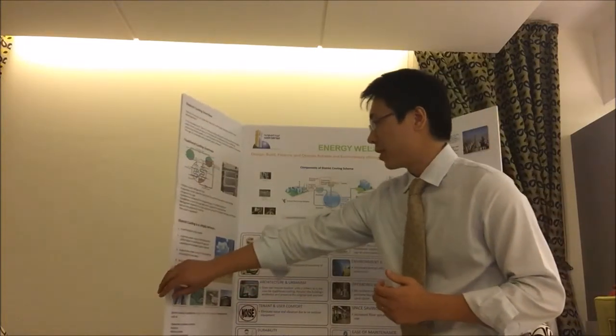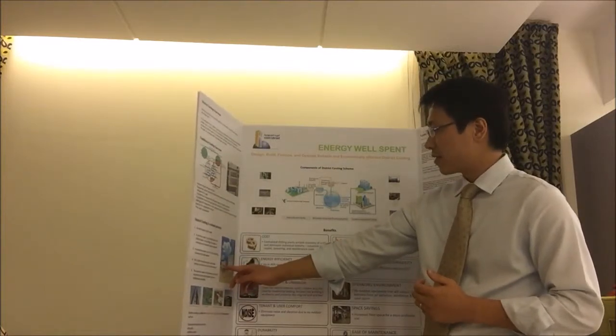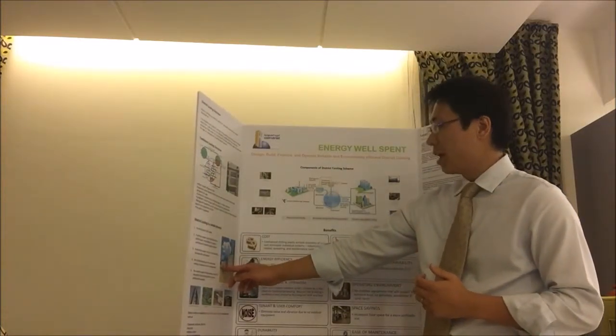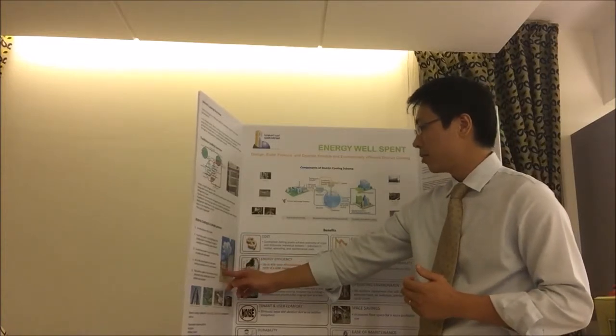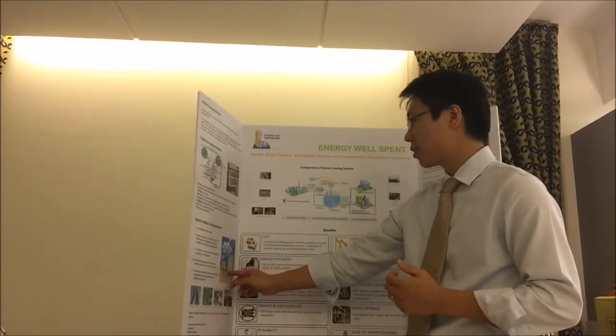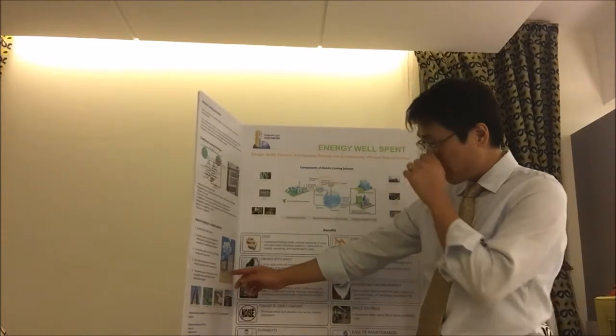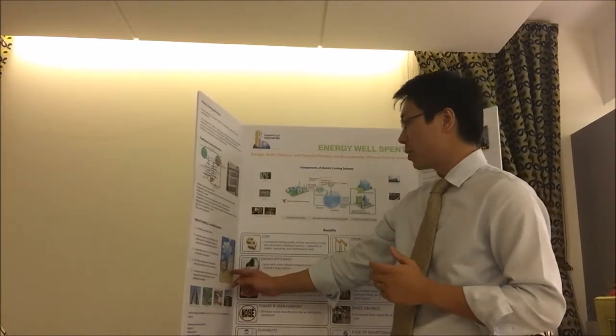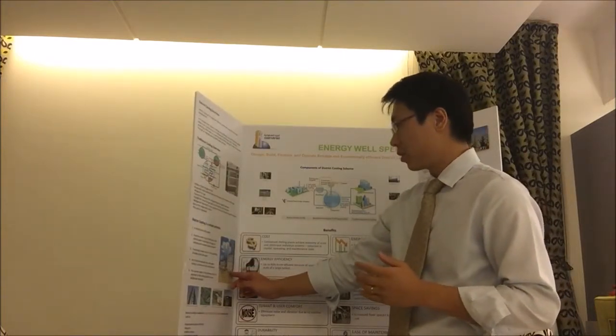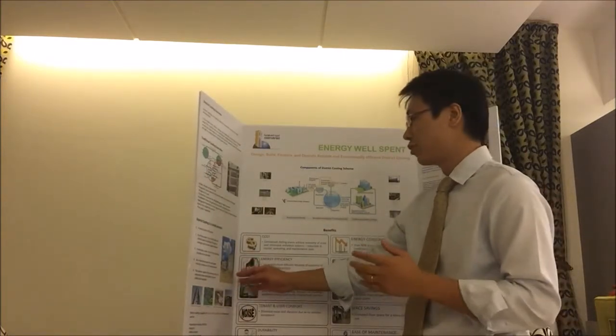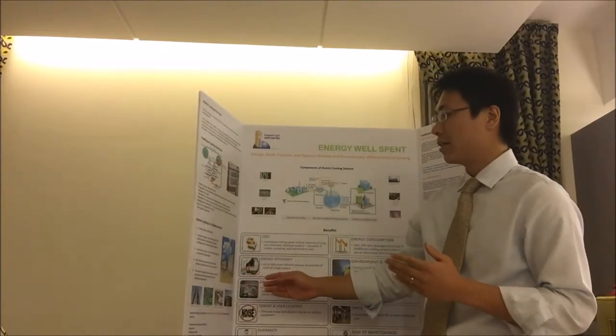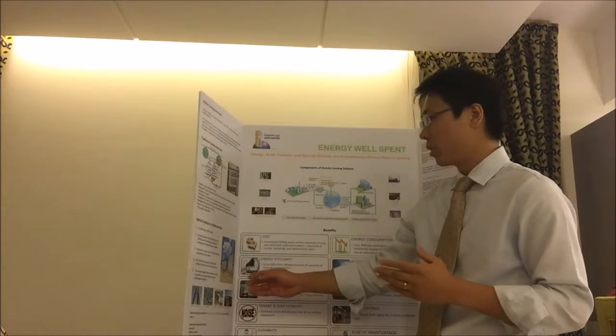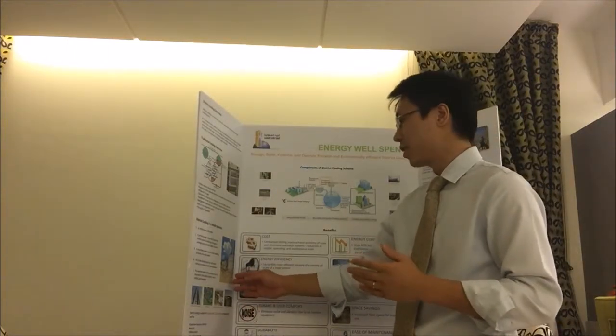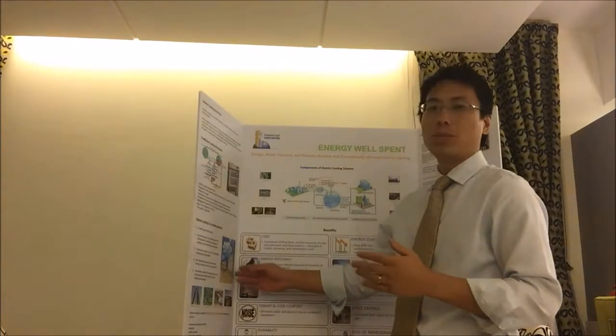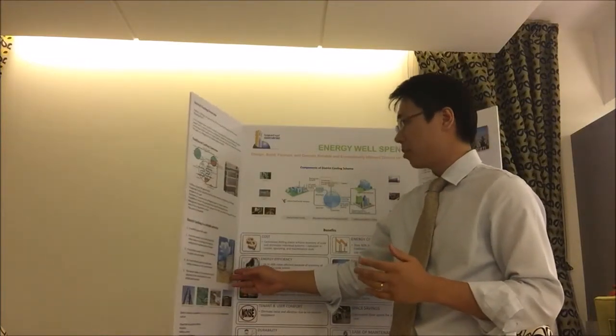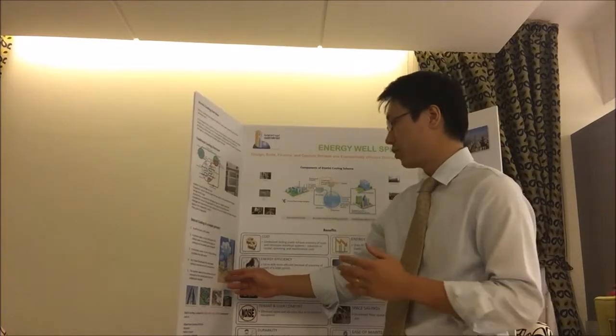For the district cooling, there's a central plant that produces chilled water, and then the chilled water is pumped to our customers through this underground insulated piping network. When the water is delivered to your building, there are secondary water circuits inside the buildings to circulate the chilled water. Air is then forced past the cold water to produce the air conditioning environment. Finally, the warm water is pumped back to the chilling plant for reuse and rechill.